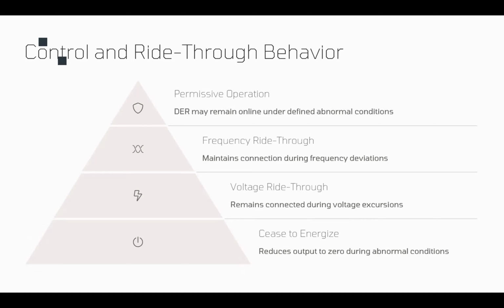Okay, so what is the purpose for this? It's preventing the system-wide cascading tripping. And most importantly, it actually provides active voltage and frequency support for the grid by staying online. The DER stays online and provides that support. In the old approach, those DERs immediately trip when they see any deviation in voltage or frequency. But now they have to stay connected and follow the ride-through requirements.